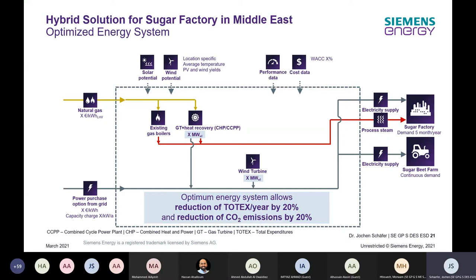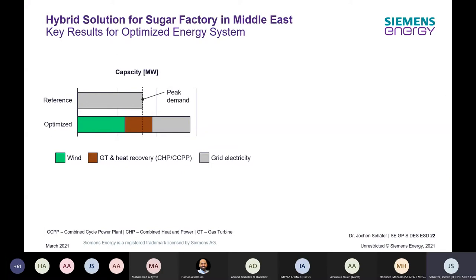The absence of solar PV gave us a headache initially, and we double-checked several times. We then understood it results from the unconventional load profiles of the sugar factory and farm: during the day there is not much electricity demand, so PV generation would largely require intermediate storage to be useful. Overall, we achieved a 20% TOTEX reduction and simultaneously a 20% CO2 emission reduction.